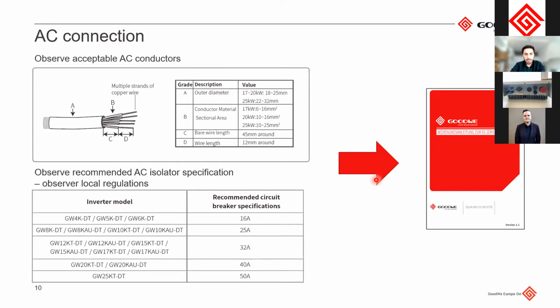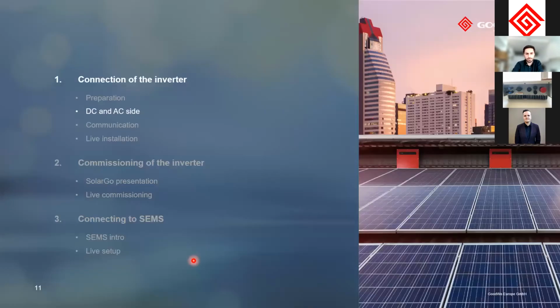For the AC connections, you need to also observe the cable sizes. This also depends on which inverter you do have, so please check this in the manual. The same thing with the AC isolator specifications. So please also check the circuit breaker, that you install the correct circuit breaker on the AC side. So depending on the model, you will need a different kind of AC breaker, or different rated.